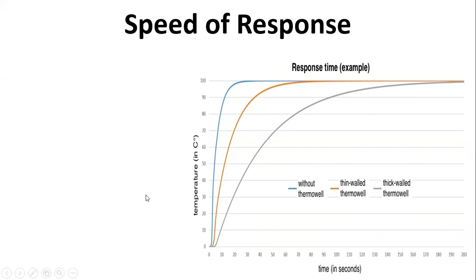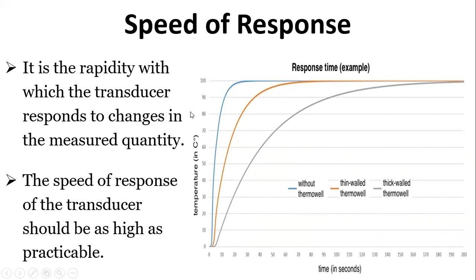So the speed of response of the transducer should be as high as practicable. Now, this is the ultimate thing. The first one is reaching the 100% steady state value in the shortest time, just 20 seconds. Whereas this one with a thin thermowell is reaching after 70 seconds, and the thick walled thermowell is reaching almost after 200 seconds. So that's the speed of response. It should be very high for a given transducer, and this should be taken care of while we are selecting it.